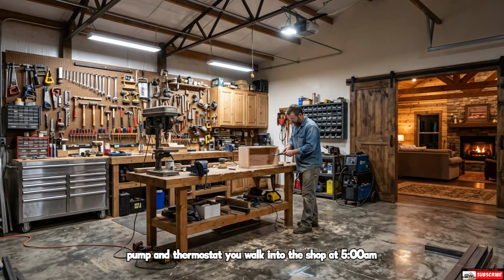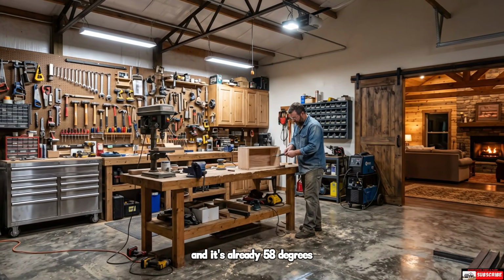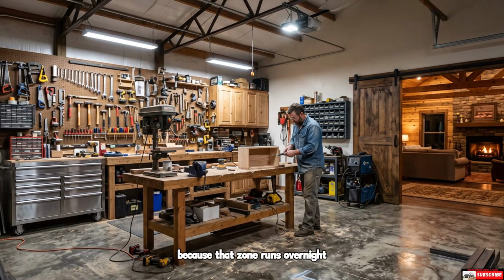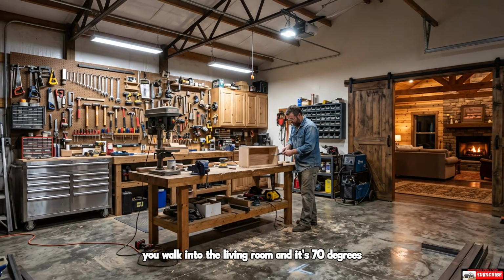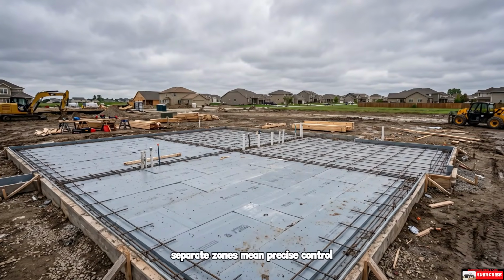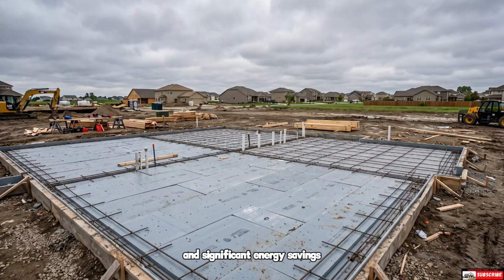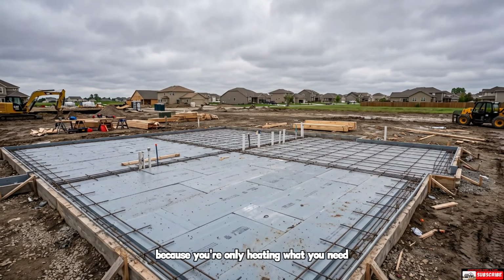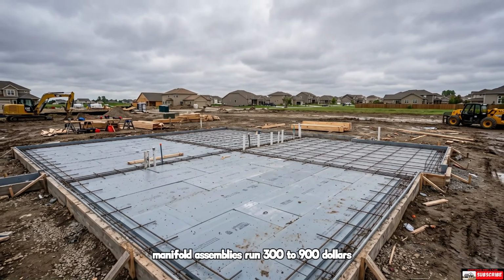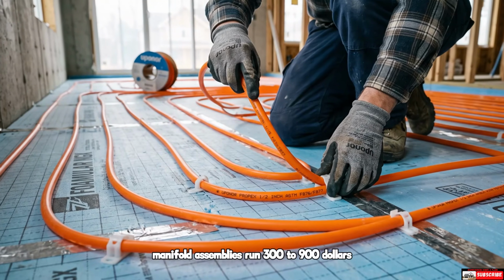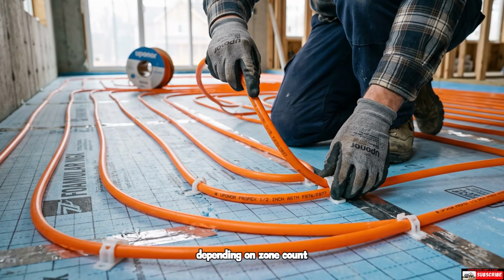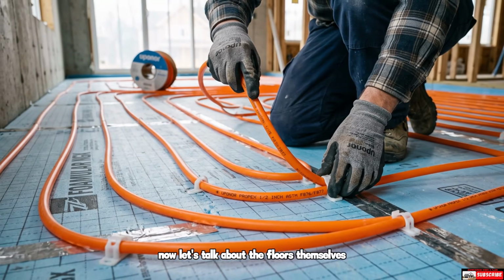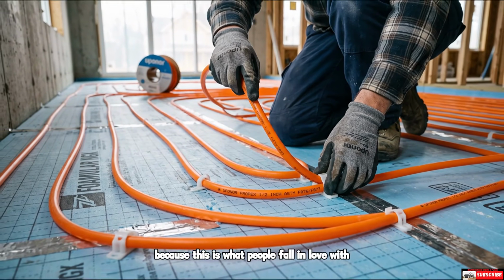You walk into the shop at 5 a.m. and it's already 58 degrees because that zone runs overnight. You walk into the living room and it's 70 degrees. Separate zones mean precise control and significant energy savings because you're only heating what you need when you need it. Manifold assemblies run $300 to $900 depending on zone count. Now let's talk about the floors themselves, because this is what people fall in love with.